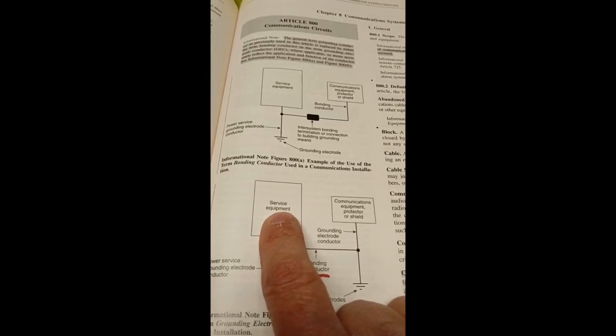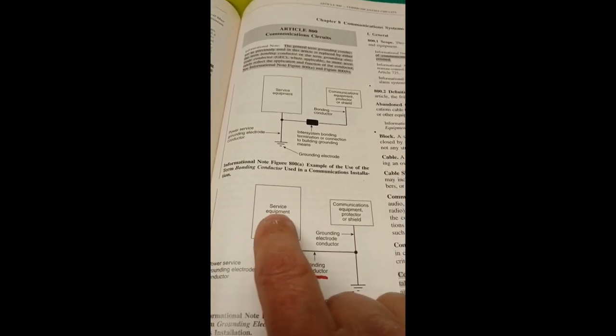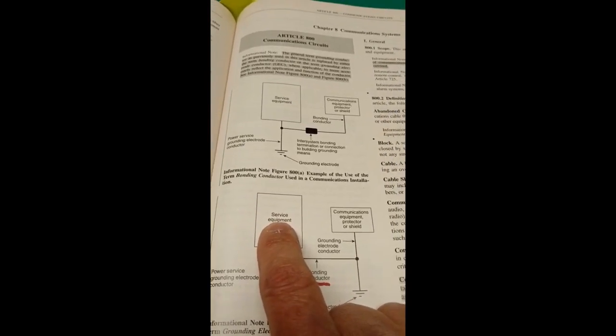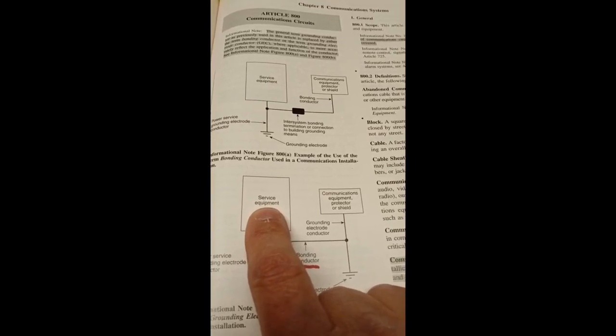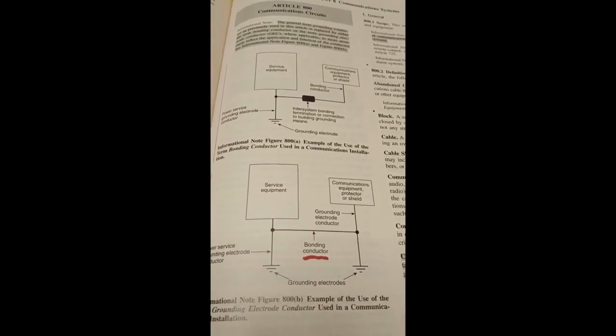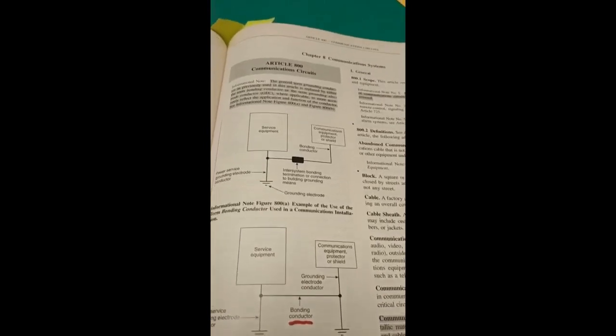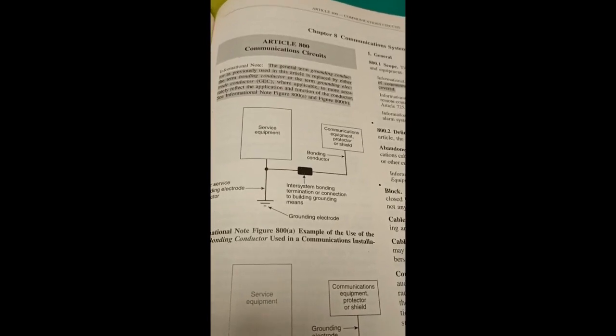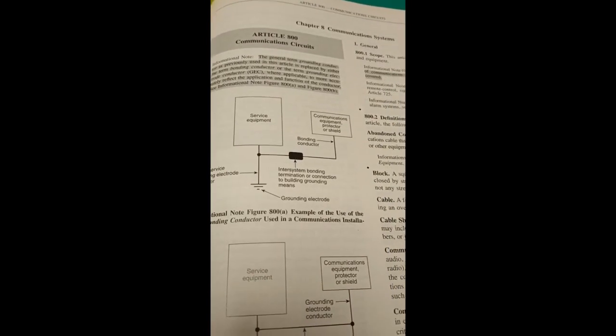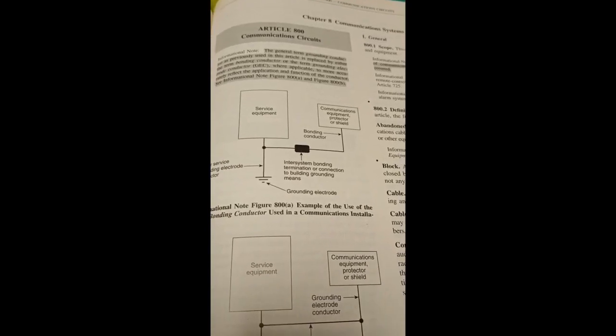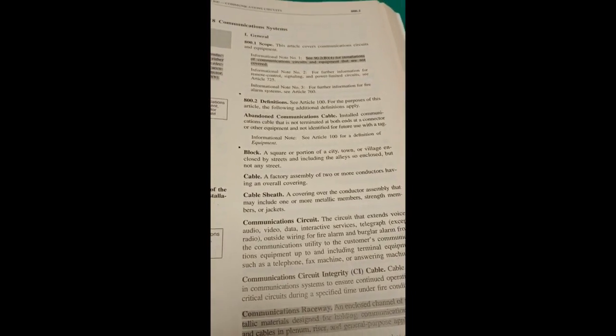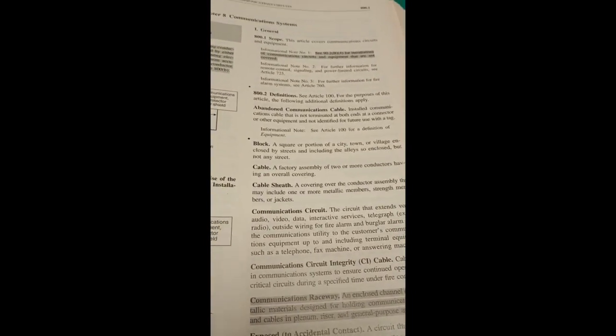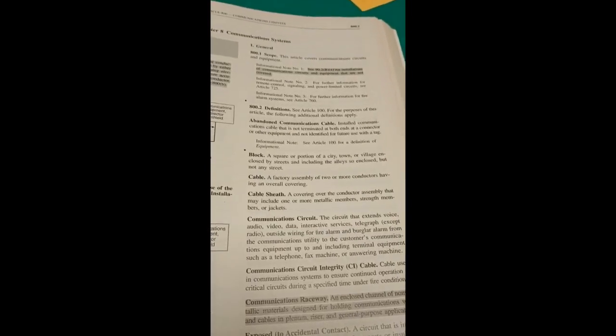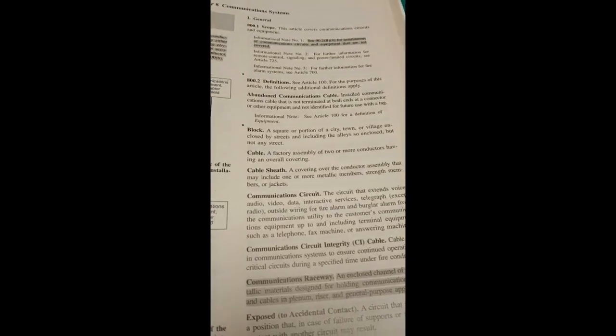Service equipment. Breaker box, fuse box, switching panel, some system box, whatever that is wired into electrical service. Not an amateur radio transceiver with a molded cord and plug and double insulated. There is nothing, I repeat, nothing in Article 800 that either mentions or specifies grounding amateur radio antennas, amateur radio coax, or amateur radio equipment. The only requirements in here are grounding towers, not antennas, and grounding for static dissipation, not grounding amateur radio equipment, which is forbidden under Article 250.24(A)(5).